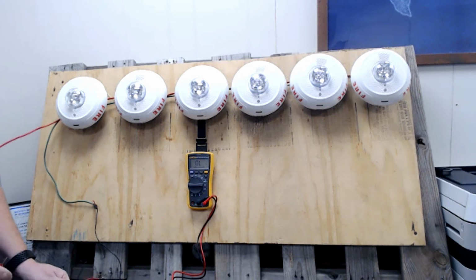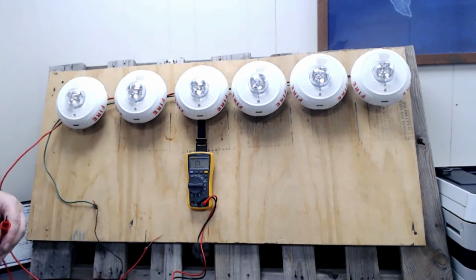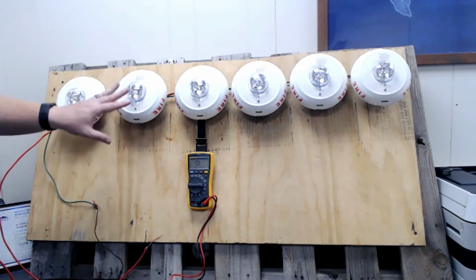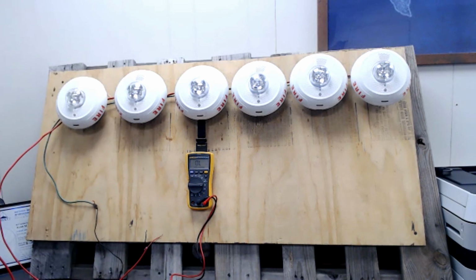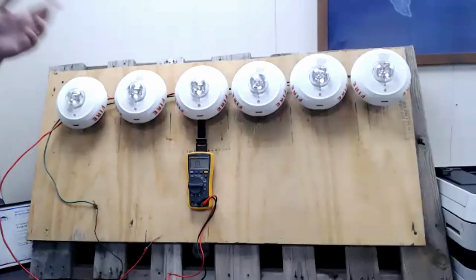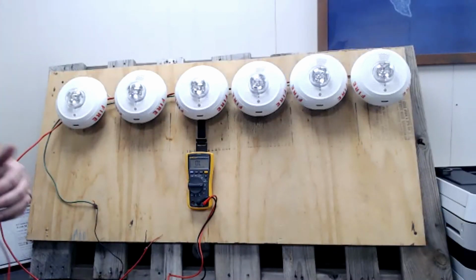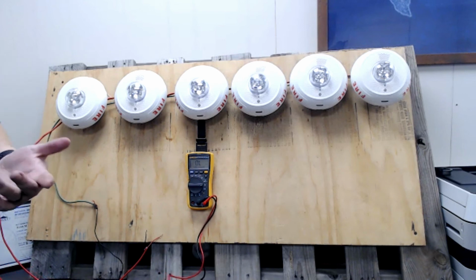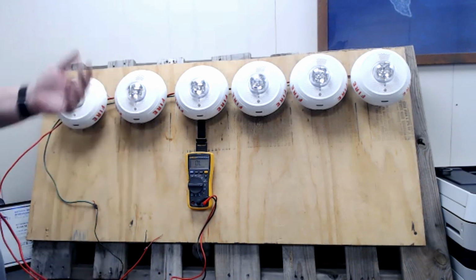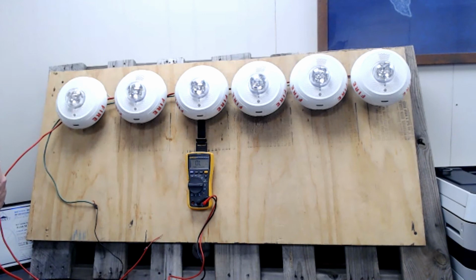Some other things can happen that can cause a ground fault like this. In this example, the wire was pinched in the device because I had too much wire in there and it got kind of shoved in there when I closed the device. Something else that can happen, we can have zip ties that are too tight. We can have sheetrock that comes in and pinches the wire up against metal studs or against red iron. There can be other things that pinch the wire to an earth ground reference. That's pretty much every time a ground fault happens, some way or another, the wire is getting pinched to another part of the building.